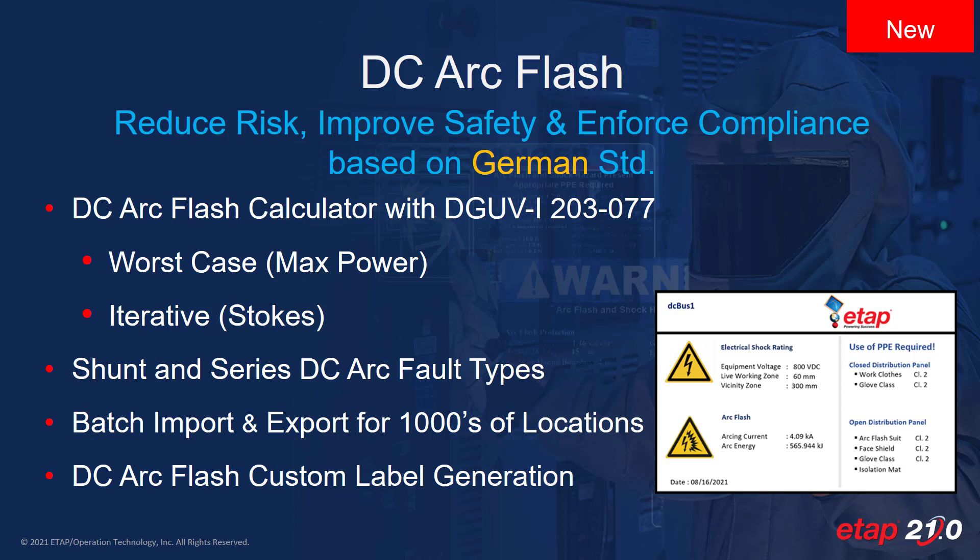The iterative method implements different anode and cathode and arc voltage gradient coefficients. The existing German arc flash calculator includes a new tab for DC arc flash analysis for both series and shunt faults, which can be extended to thousands of locations by means of batch instruction files.